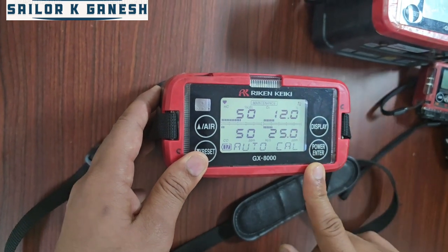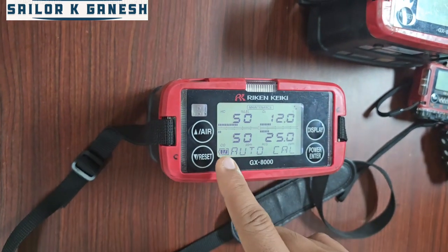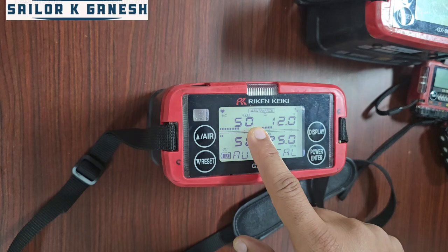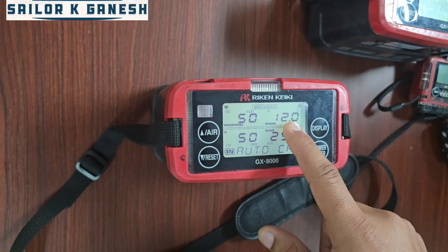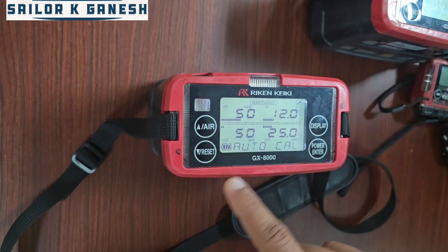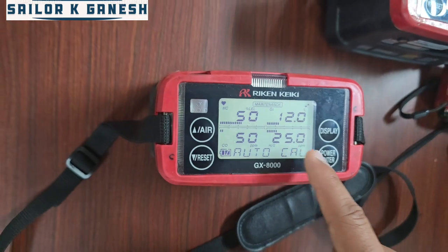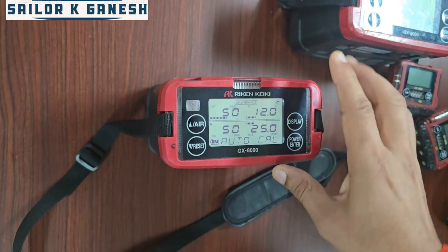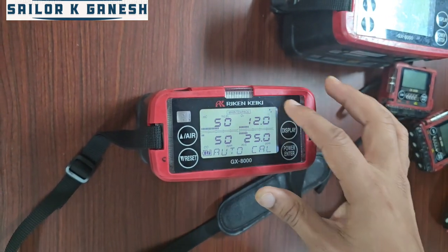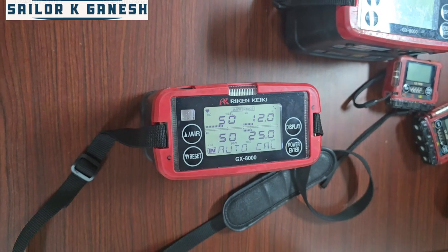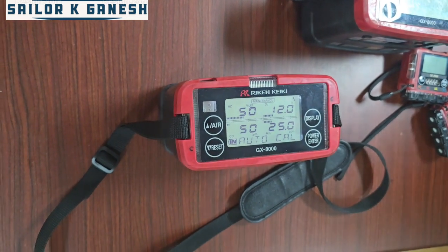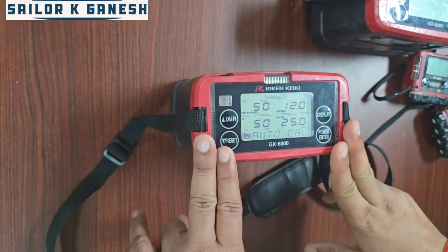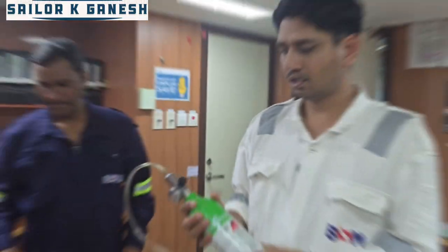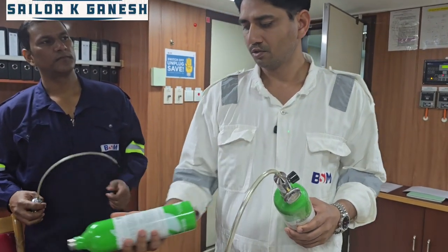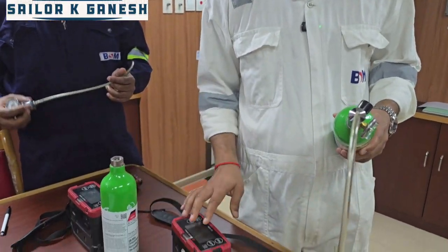Press enter. Here we have 4 sets of gas: hydrocarbon 50% LEL, oxygen 12%, carbon monoxide 50 ppm, and H2S 25 ppm. So we need to calibrate this equipment with all these gases available. We have a span bottle over there. With that bottle, we will calibrate this equipment. I will show you the span bottles we have on board. So this requires 4 sets of gas.